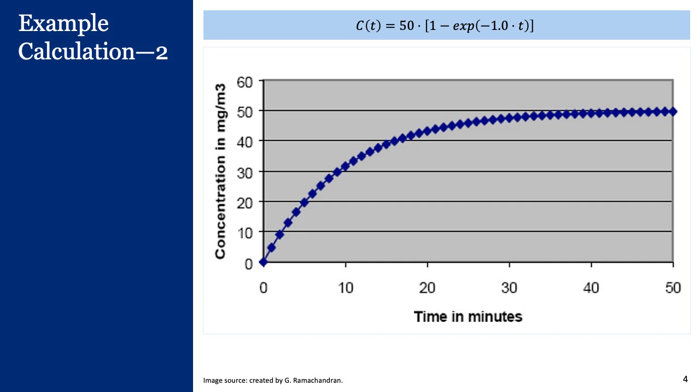If we go back to the generation rate, that is 1,000 milligrams per minute, and the ventilation rate is 20 cubic meters per minute. So 1,000 divided by 20, that is 50. So that's the value of G divided by Q. In the exponent, we have minus Q over V. So Q is, again, 20 cubic meters per minute, and the volume of the room is 200. So we get Q over V as 0.1.